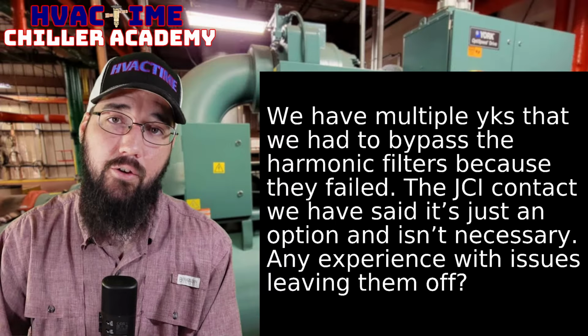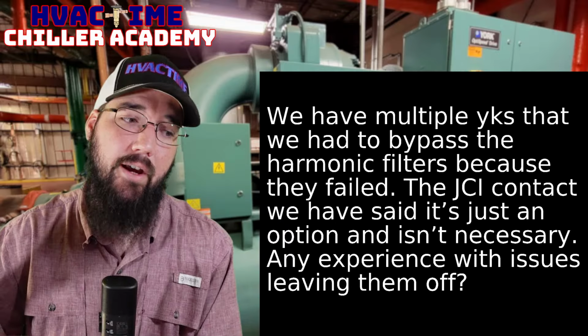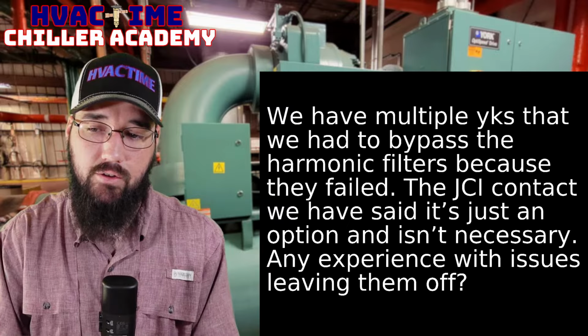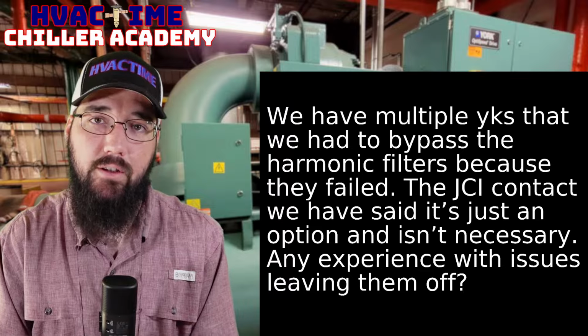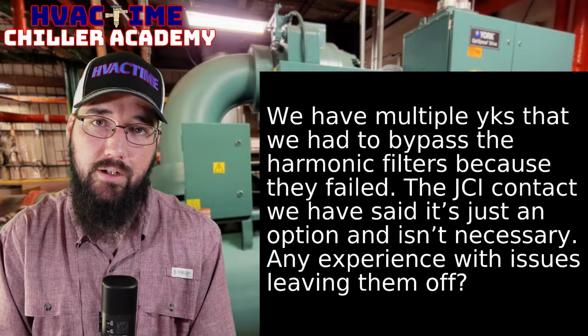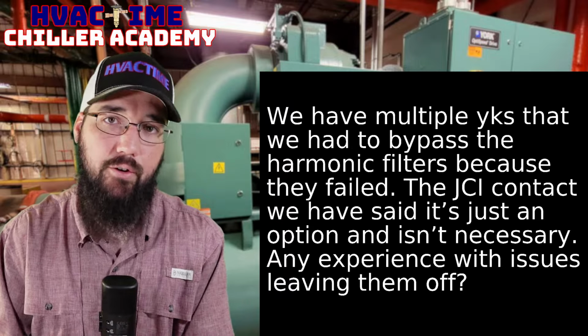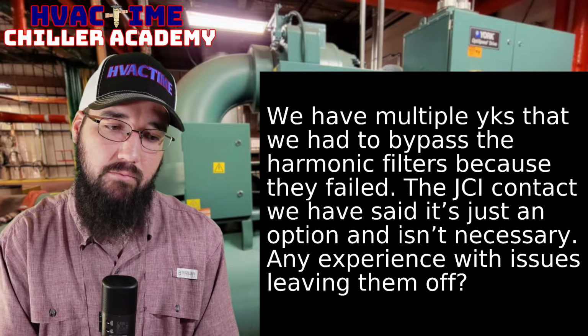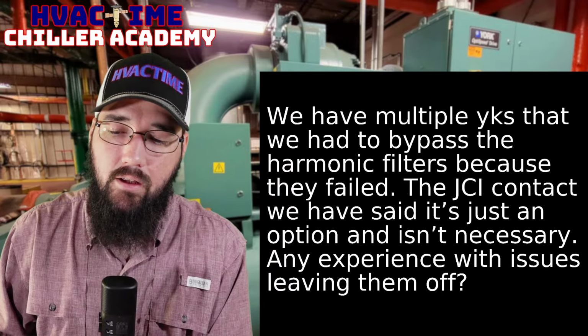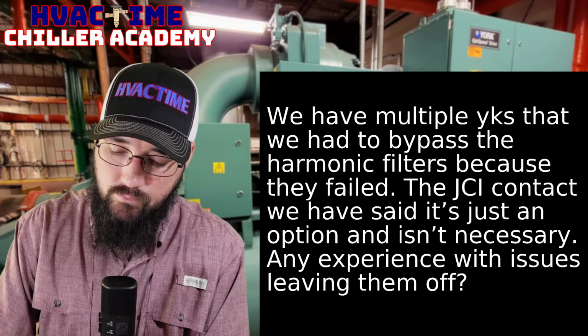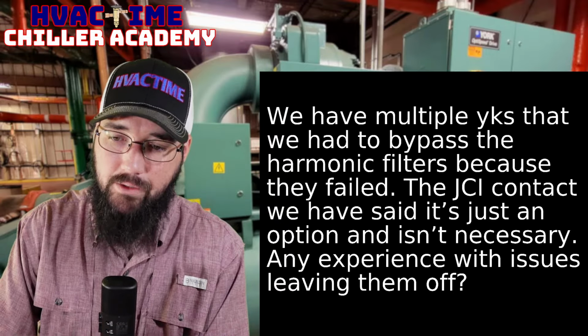It can affect other drive assemblies. It can affect just other power sources. Like it's static noise in the electrical grid, right? It is what it is. It creates problems and failures, and our equipment doesn't want that. So that's what the line reactor is doing.